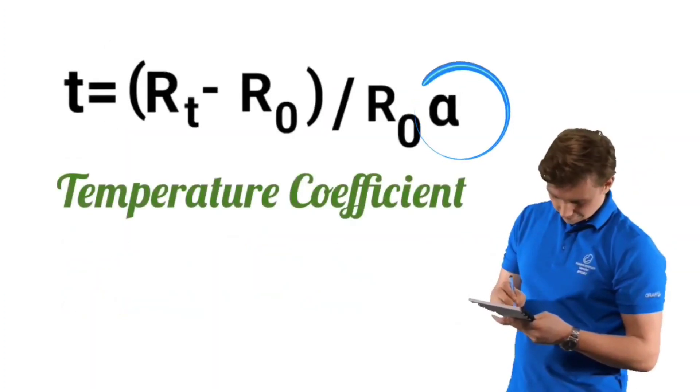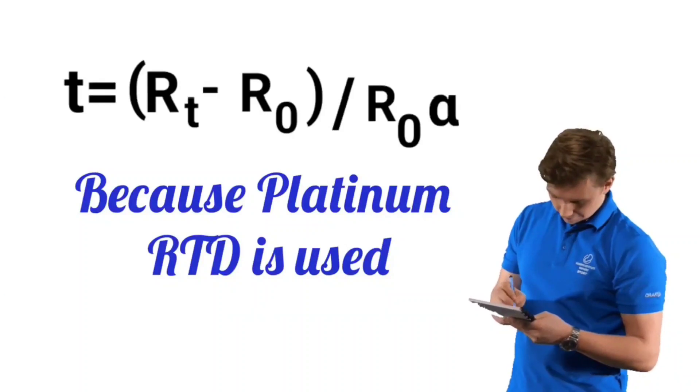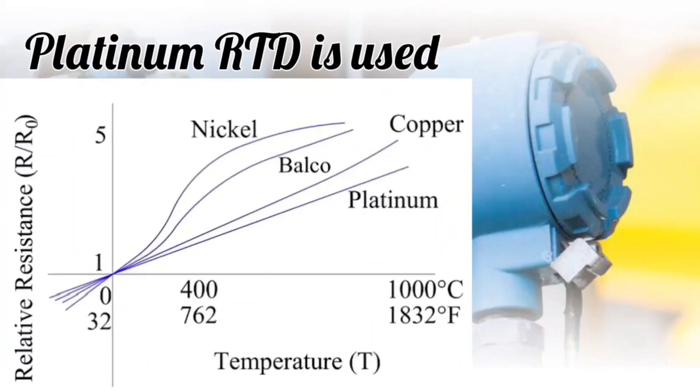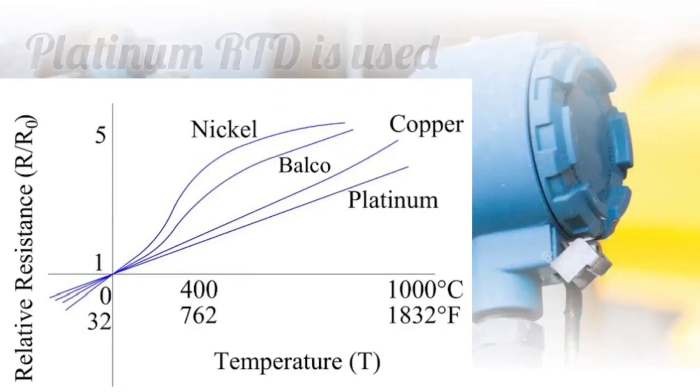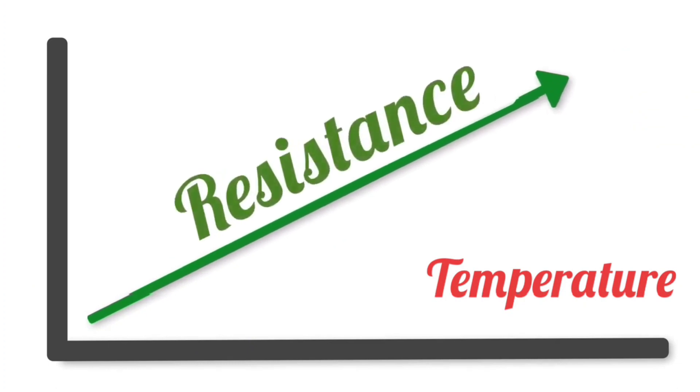Here alpha is the temperature coefficient, whose value is 0.00385 for platinum. Here alpha is taken for platinum because we use mostly the platinum RTD. The platinum RTD is used because the resistance of platinum varies most linearly with temperature as compared to other materials. How does it vary linearly means as the temperature increases, the resistance will also increase accordingly.